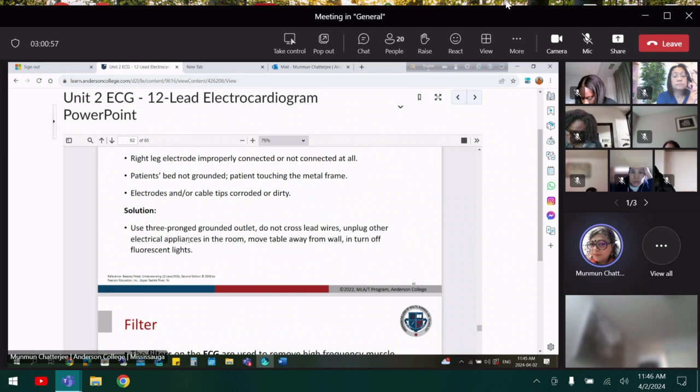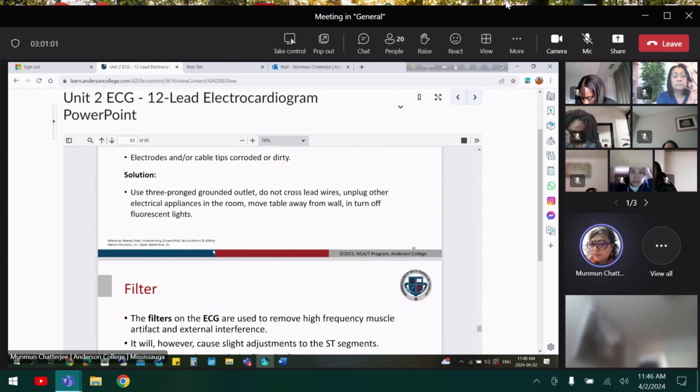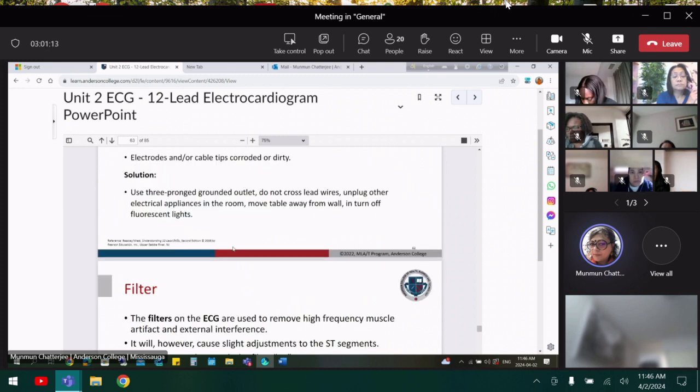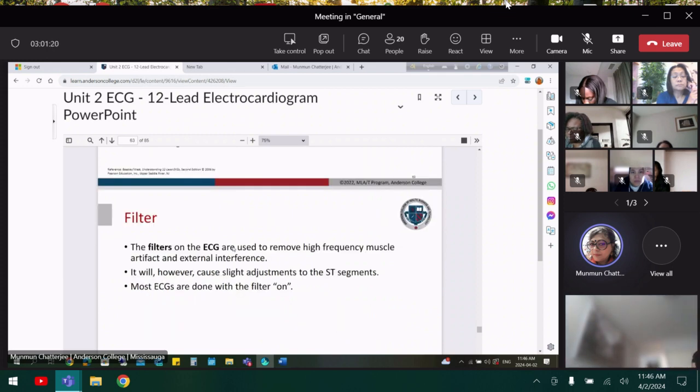This alternating current we rarely see because nowadays ECG machines are so good. Even if you keep a cell phone, hearing aid, or pacemaker near, you won't see the extra spike. But other things, it doesn't show the alternating current. If it really shows, that's a grounding problem, or maybe somebody has some metal chips or devices which are picking up the extra current.